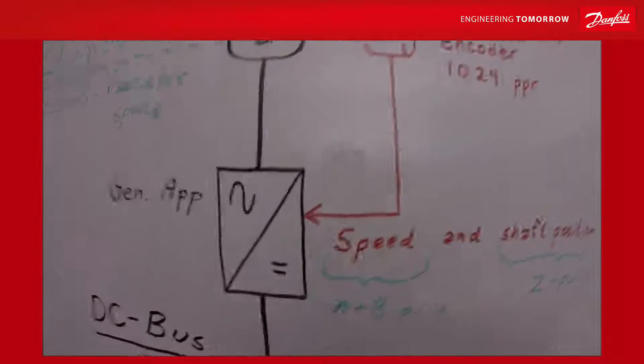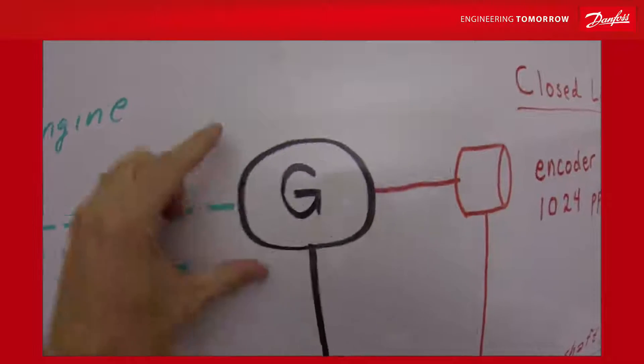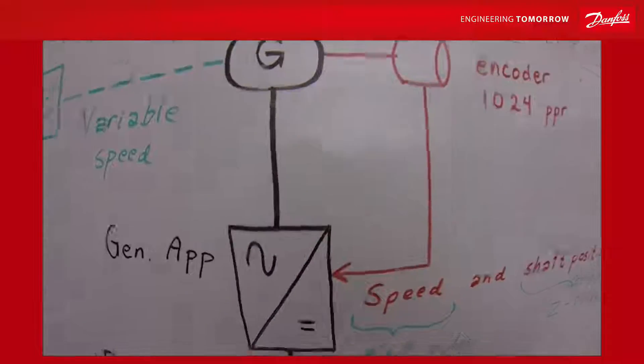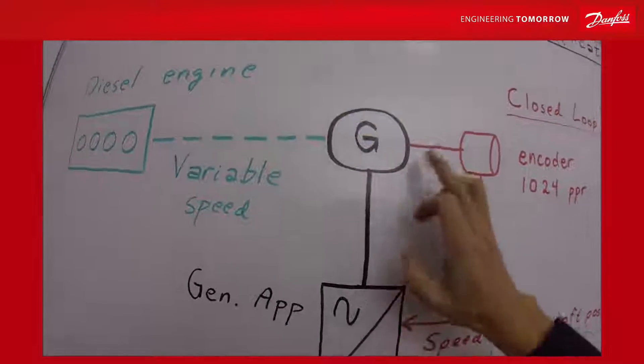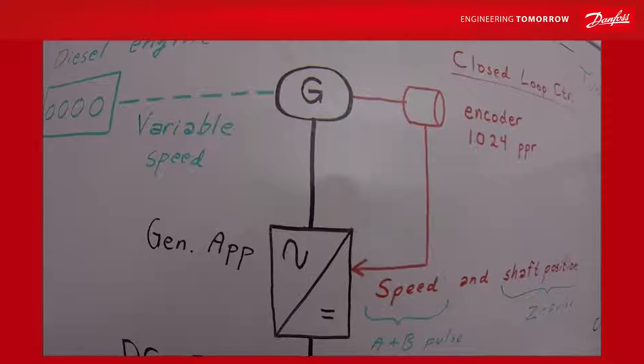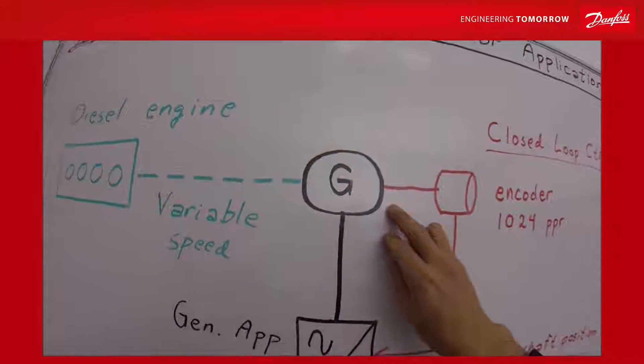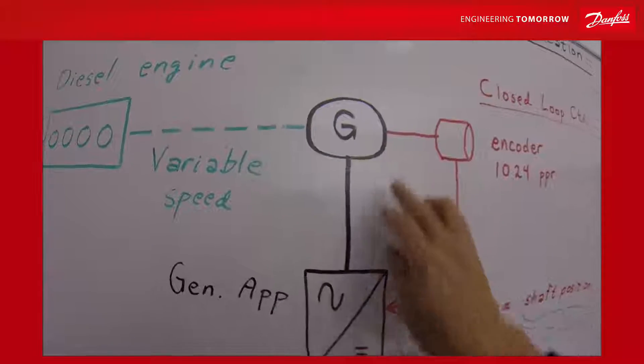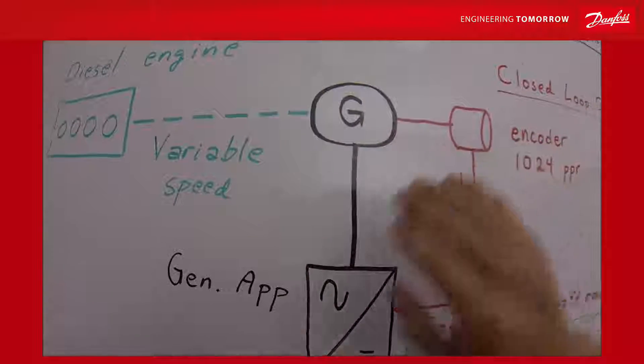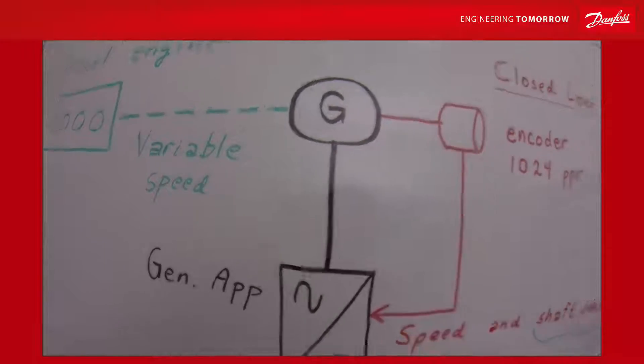For our drive this means that the drive needs to control the generator in a closed loop motor control. To handle the generator like motor control, the drive needs precise information about the motor characteristics. This means the motor nominals but also identification runs to identify the back EMF curves and the impedance of the motor.